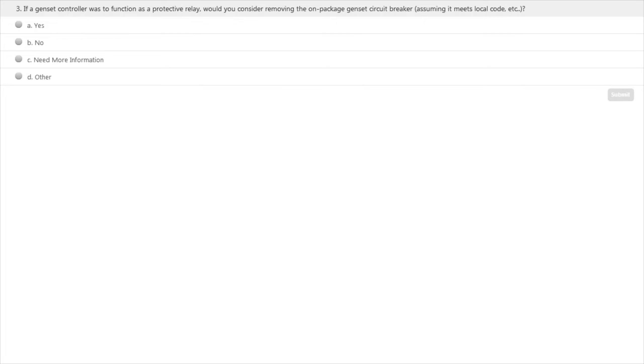So actually they do, if the generator set had been tested and verified to meet their design requirements without the breaker. For an example, Caterpillar can provide a UL 2200 rated package without a generator mounted circuit breaker, because we have shown that the protective settings that we have with our overcurrent protection provide the same functions and are able to shut the unit down. So that is possible to be ordered based off the customer's request.